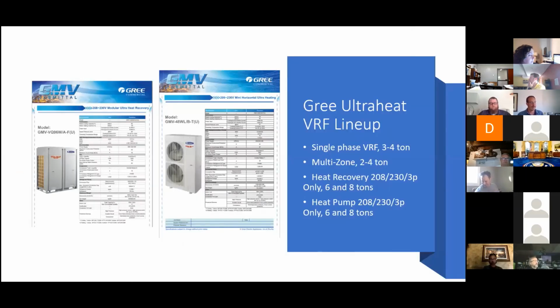Gree also has, not a full line, they're getting there, in UltraHeat. So they have a 6-ton and an 8-ton in 3-phase. And they also have an UltraHeat single-phase VRF heat recovery. So if, let's say, instead of the multis, you want to have a single-phase 4-ton, you can pipe 4 units in series off of one in single-phase. This could be a straight up and down apartment building, or a home where they wanted individual units in the rooms instead of a furnace, for example.